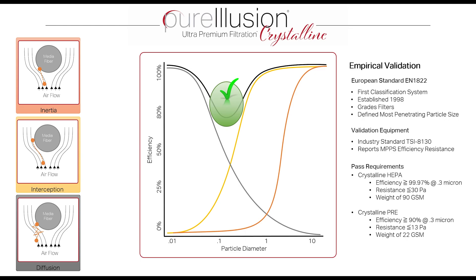Crystalline is validated by a TSI 8130. We perform an empirical validation using the TSI 8130 to provide assurance of the most penetrating particle size captured at an efficiency rate greater than or equal to 99.97% at 0.3 microns, with a resistance less than or equal to 30 pascals on a filter weight of 90 grams per square meter. The Crystalline pre-filter is equally impressive, capturing greater than or equal to 90% efficiency at 0.3 microns with a resistance less than or equal to 13 pascals on a filter weight of 22 grams per square meter.